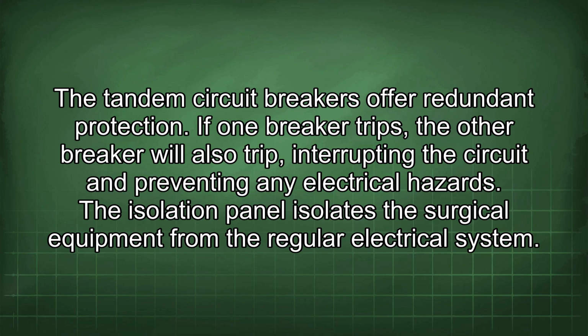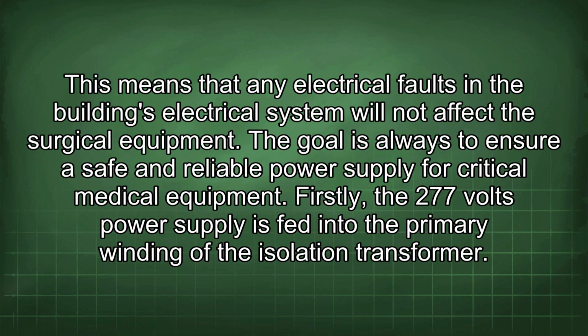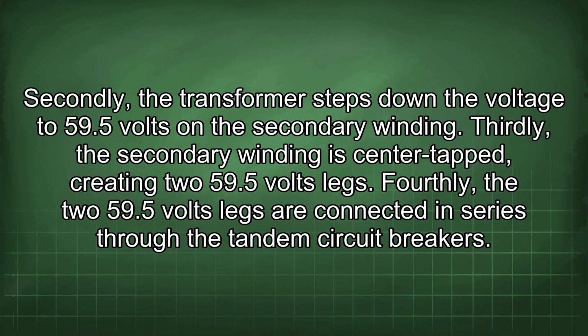The isolation panel isolates the surgical equipment from the regular electrical system. This means that any electrical faults in the building's electrical system will not affect the surgical equipment. The goal is always to ensure a safe and reliable power supply for critical medical equipment. Firstly, the 277 volts power supply is fed into the primary winding of the isolation transformer. Secondly, the transformer steps down the voltage to 59.5 volts on the secondary winding.